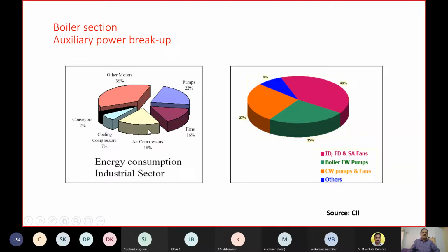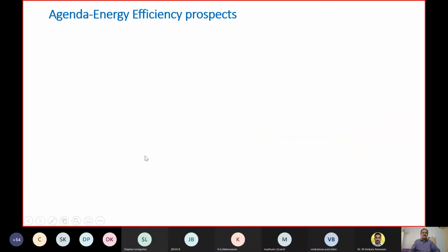Similarly, in the case of an industry, you will find that variable torque loads contribute almost 66% of the total power. So we talk in terms of air compressors, fans, and pumps, almost two-thirds. Other motors will be the process motors, like shape-changing motors in the case of raw material to finished goods. Similarly, material handling, conveyors, and so on. So this is how the motors' own consumption is laid out. We will come back later to discuss and understand more about these variable torque loads or centrifugal loads, which are used as pumps, fans, and compressors or cooling compressors, refrigeration compressors.